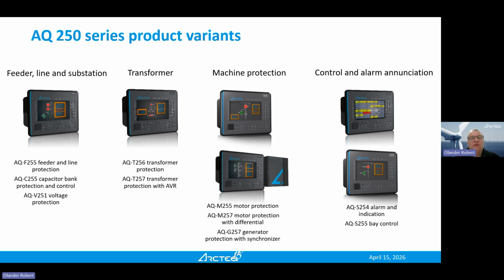And then transformer protection, of course, with or without differential protection, with or without voltage protection, or with or without AVR. That's an option which you can add if you want to integrate AVR in your transformer protection. You can also have it separately in a smaller device. Machine protection, so we have quite full specification with motor and generator protection. Also here with or without differential protection and so on. And actually we are quite big because we are working a lot with the industry also.